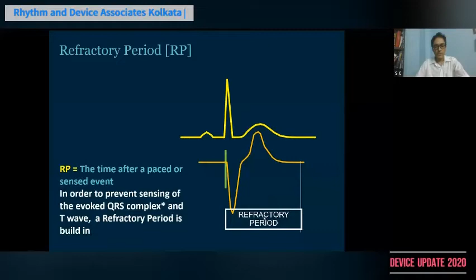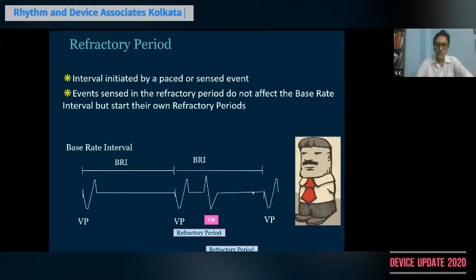You have to understand that a refractory period can be initiated not only by a paced event, it can also be initiated by a sensed event. So suppose this is the ventricular pace complex to your left, it initiates a base rate interval. Again, a ventricular paced event occurs at the end. Suppose for discussion's sake this third complex is a ventricular ectopic which falls into the refractory period. This will now not lead to resetting of the ventricular base rate. It will be sensed by the pacemaker and given an annotation of VR, which means ventricular event in the refractory period, but it will not reset your base rate interval.